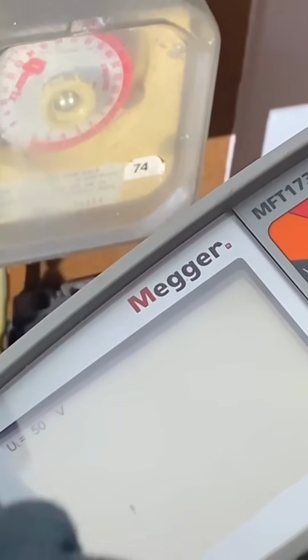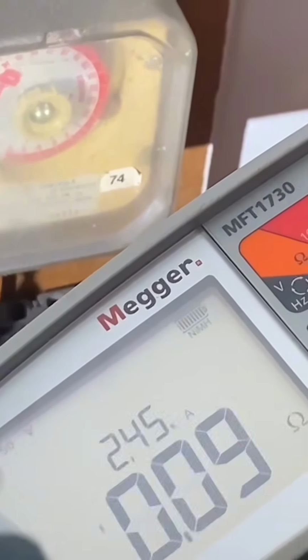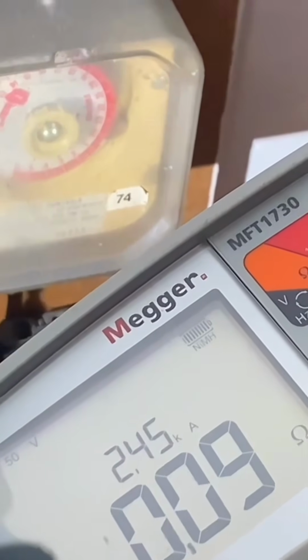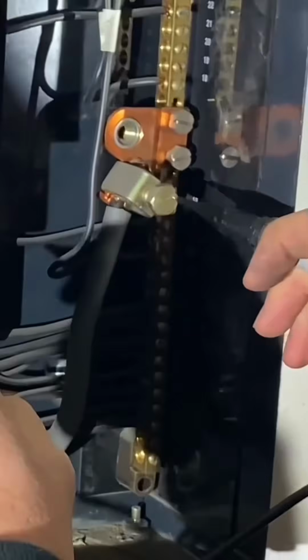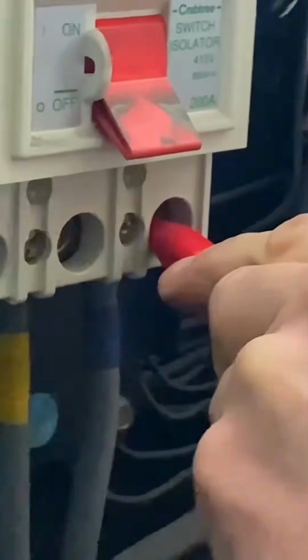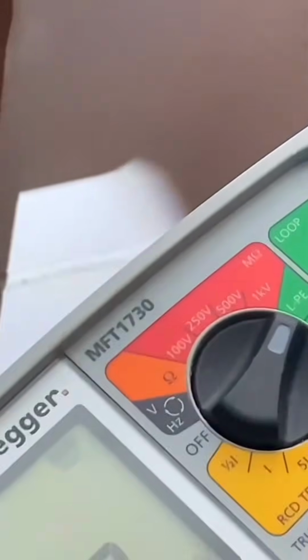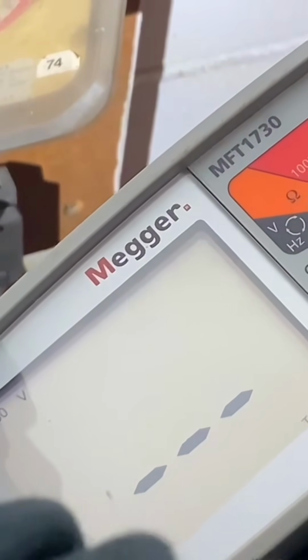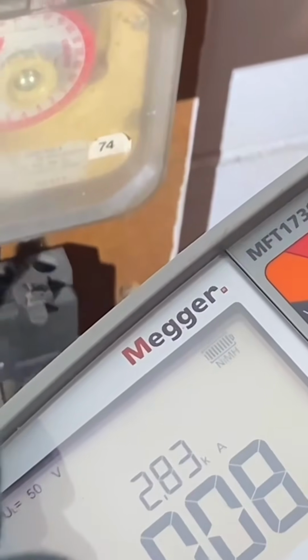Of the 3 readings we take, which one are we going to record? So it's just the highest reading. Okay, so we've got to remember we've got 0.08, now we've got 0.09, so that's now the highest one. Probe back on. If you notice, every time I physically take your probes back off in the right order, take them exactly off, the same as we do for supply polarity and safe isolation. Yeah, right. 0.08 of an ohm.